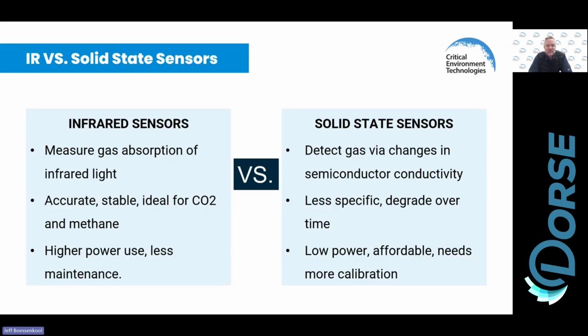What are the specific gases and concentration levels? Again, using our study guide, we can use this as a guide to figure out what are those concentration levels and set point levels that we need to be concerned about. Sensor technology, right? Why would we use an infrared sensor over a solid state sensor, right? In a refrigerant application, what would be the best sensor for that application?